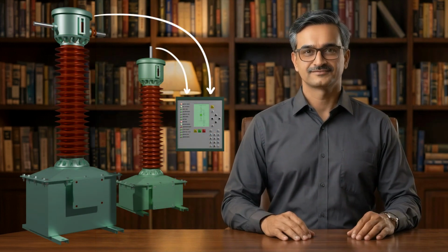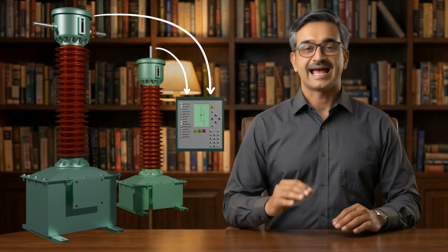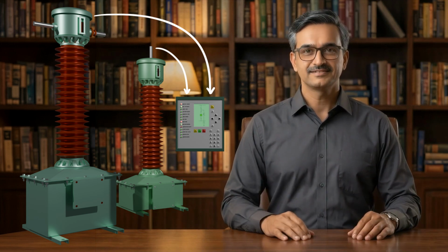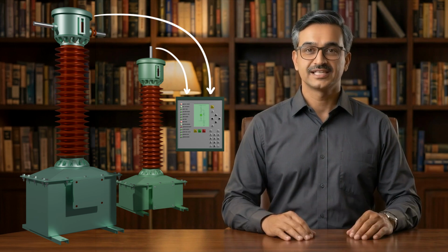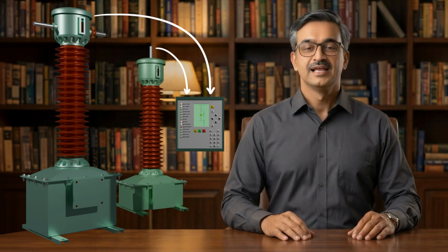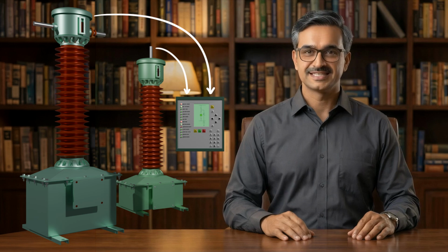Now, the basic concept of a BCU is very simple. It has a central processing unit, or CPU. It is a single modern unit that contains a CPU along with a number of input terminals and output terminals associated with it. Actually, a conventional control panel receives different signals from a bay of the substation. It receives current signals from the secondary of the current transformers associated with the bay, and it receives secondary voltage signals from the potential transformers associated with that bay, or sometimes from the common voltage transformer of the system.